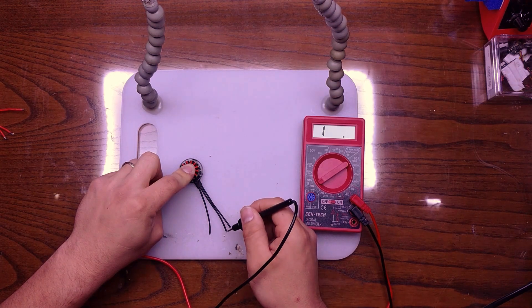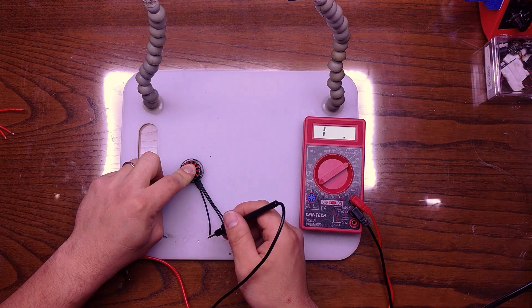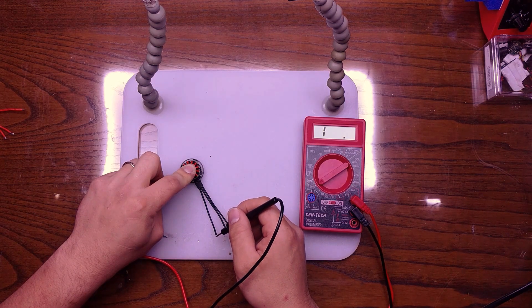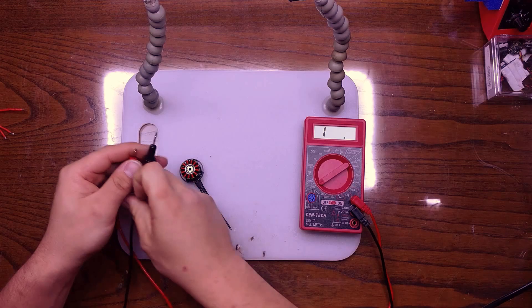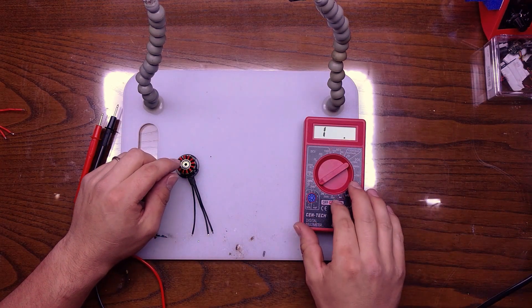And that's what you want to see right there. You do not want to see it go to zero. You do not want the multimeter to show continuity. And this is just a simple way to test your newly wound stator for any shorts or problems.